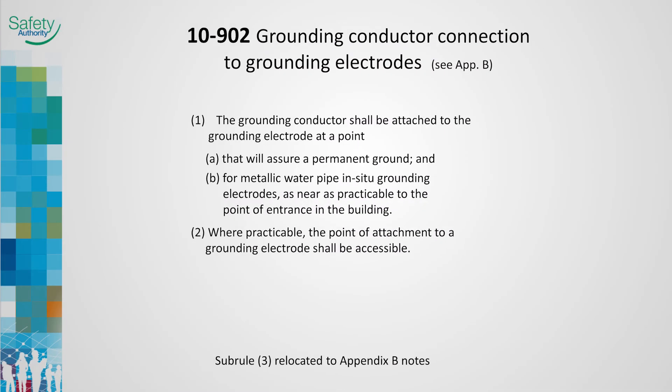This rule was formerly titled Grounding Conductor Connection to Water Pipe Electrodes. The title and scope has been changed and this rule now applies to all electrode types. Former sub-rule 3, found in the 2012 code, has been relocated into Appendix B as notes. Sub-rule 3 describes how the cold water system was to be bonded and made electrically continuous.